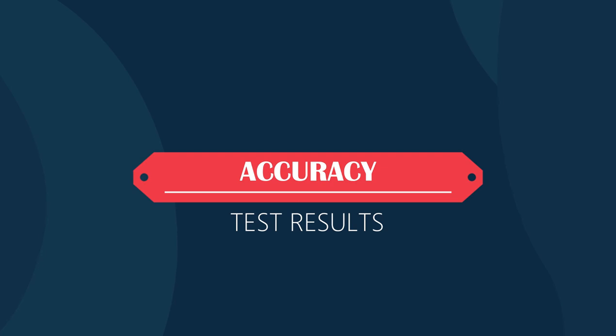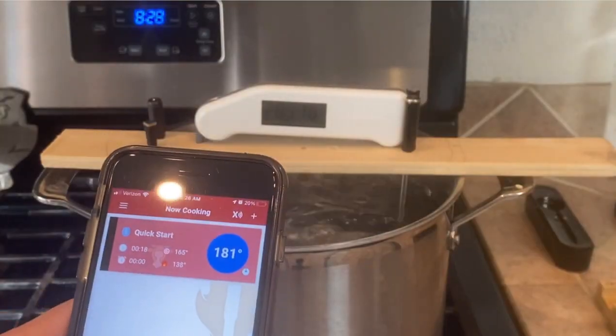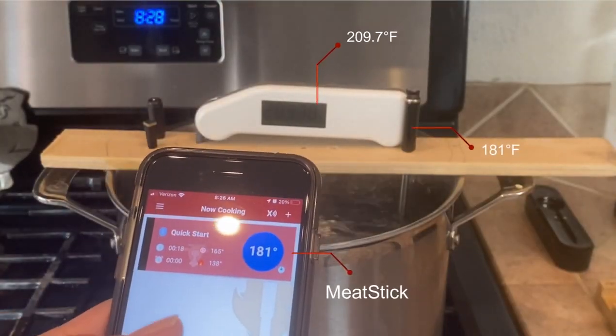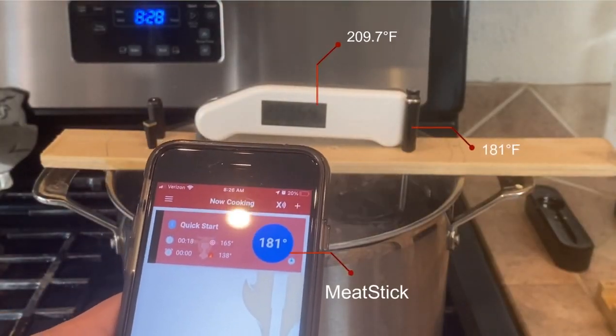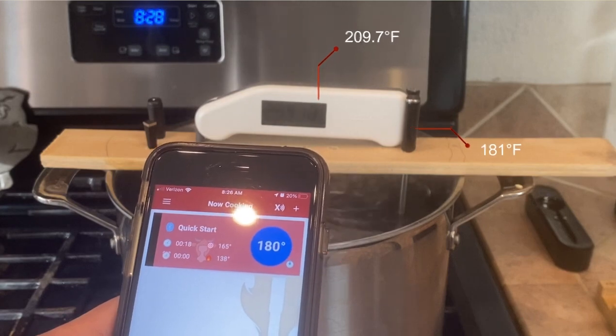What we found is that in the boiling water test, when we put some of these in, if the probe didn't go far enough into the water, you were getting a reading that was not accurate at all. So that was one of the main things that's different in these probes versus your traditional thermometer probes.